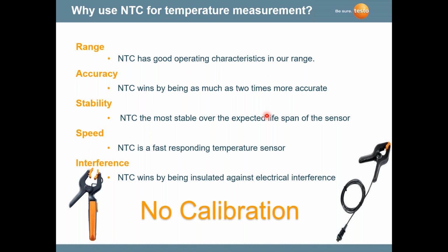Nice thing about NTC probes is they have very good range for refrigeration and air conditioning systems. They are much more accurate than thermocouples. They're more stable, and they're very quick on response time. The biggest thing here is that NTC probes never need to be calibrated. They are calibrated once at our factory, and they will last the life of the instrument.